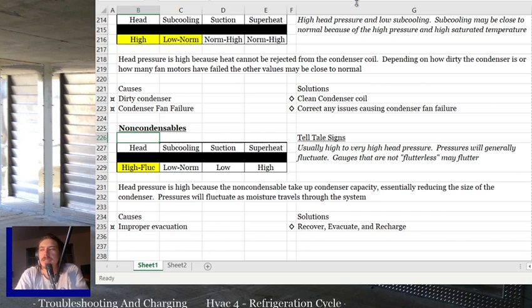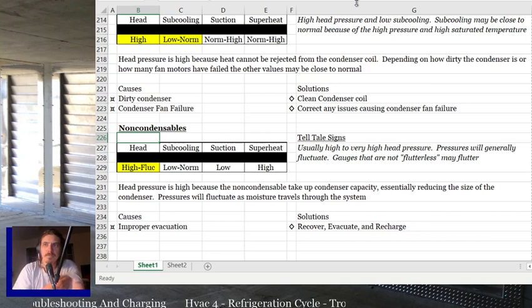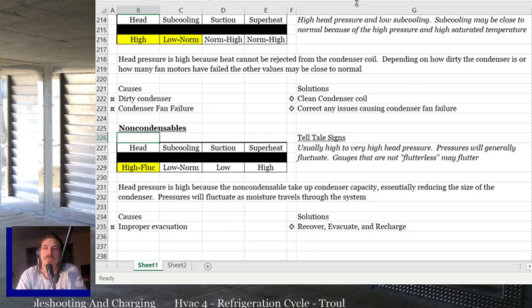If you've got very little refrigerant and more nitrogen or something than anything else, you'll have almost no compression ratio, because the nitrogen won't compress, it'll just stay there, and it'll look almost like an overfeeding metering device, but the pressures will be weird, so you'll know that's not what it is. So typically you'll see the pressure fluctuation. If you don't see that, it'll just be super high pressures, and everything will go wonky when you try and pull out the charge if you think it's overcharged or something.